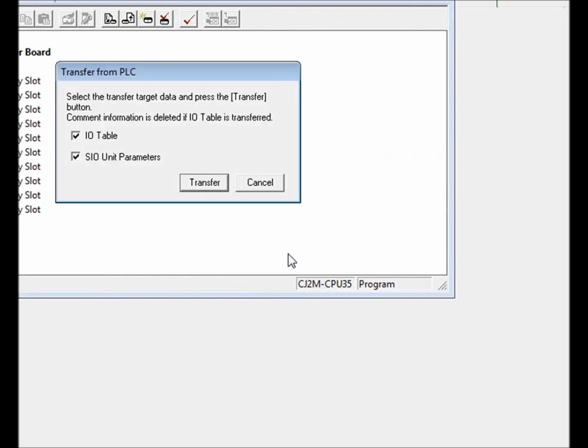Make sure both I.O. table and S.I.O. unit parameters are selected. This will allow CX Programmer to upload the I.O. table and special I.O. settings after the I.O. table is created. Now press the transfer button.